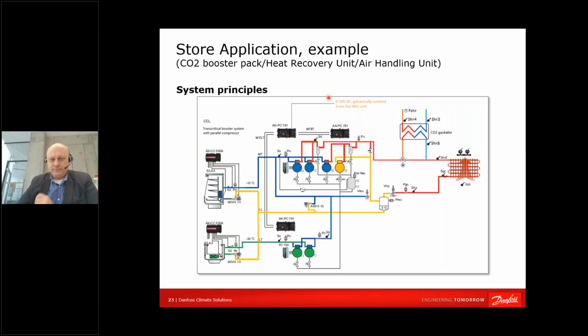Typical application. A few words about a typical application which is used nowadays without heat recovery. There would probably be 2 blocks of mechanics inside. They would contain a three-way valve, which is bypassing hot gas either to the recovery or to the gas cooler. Typically, here we would have a tank with a coil or something inside, and that coil would be used to heat domestic hot water.